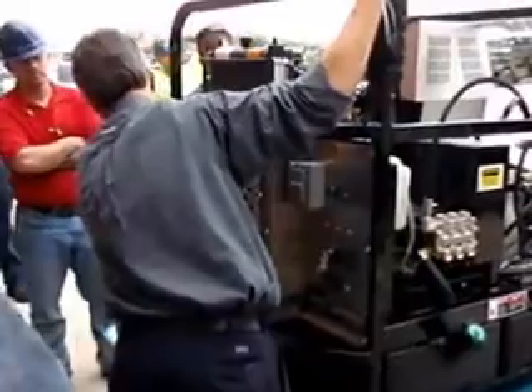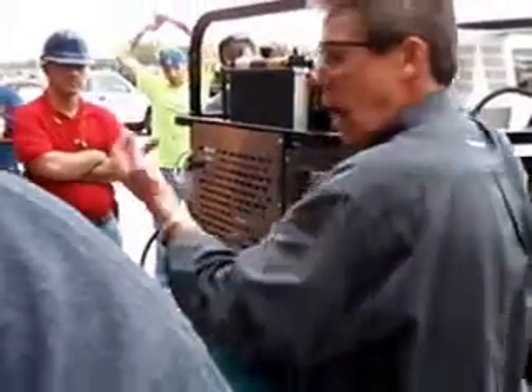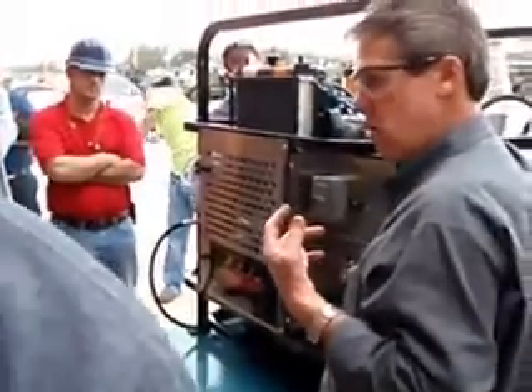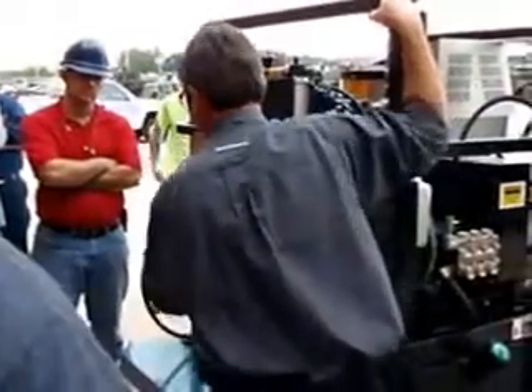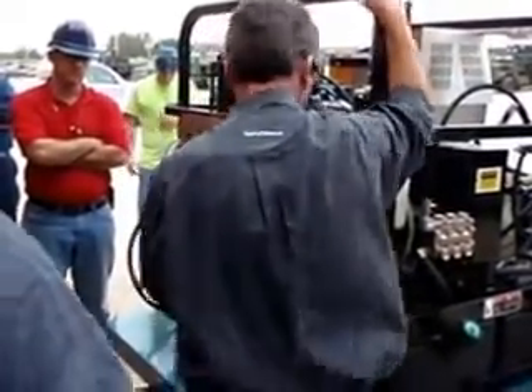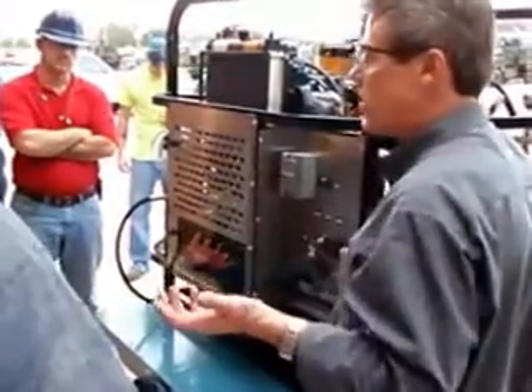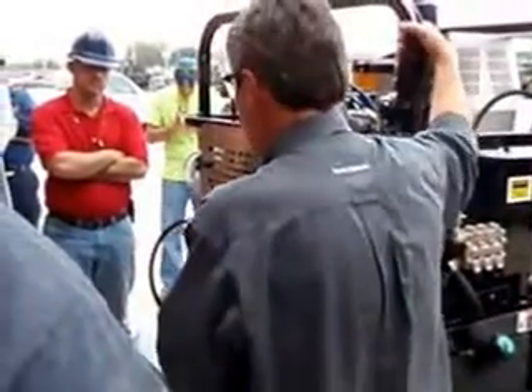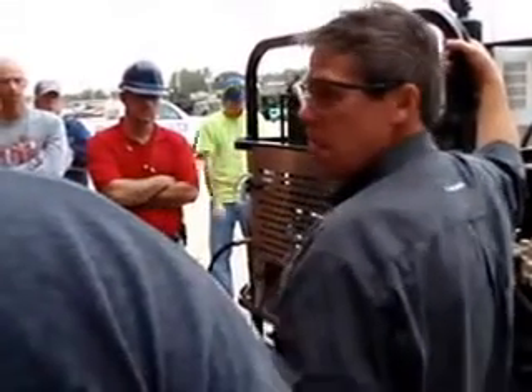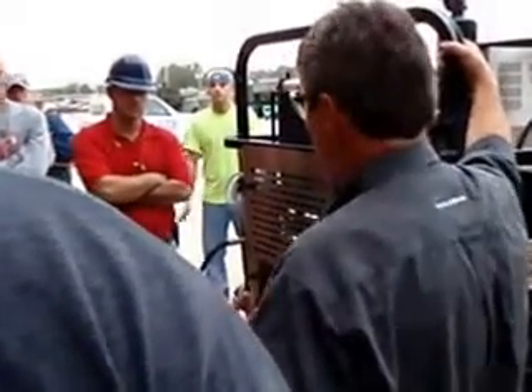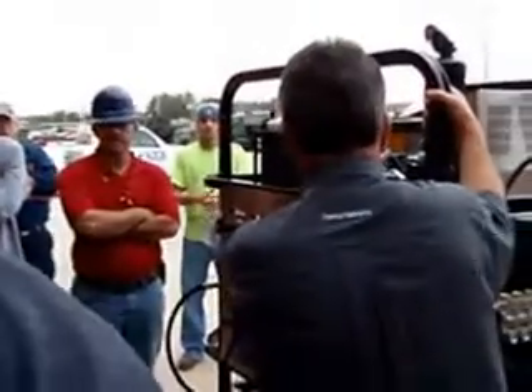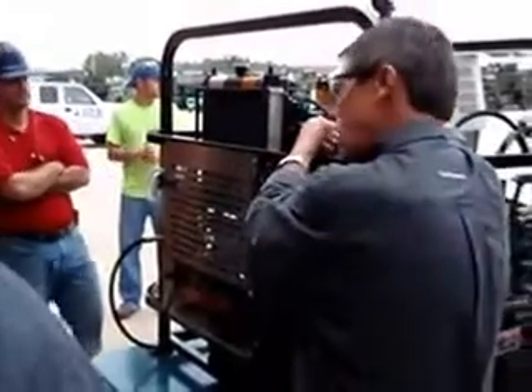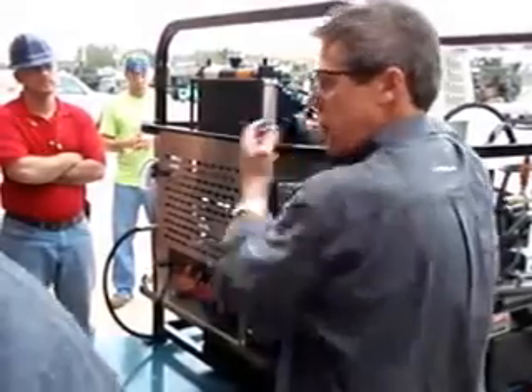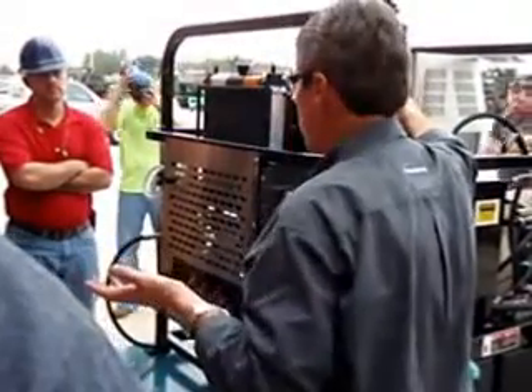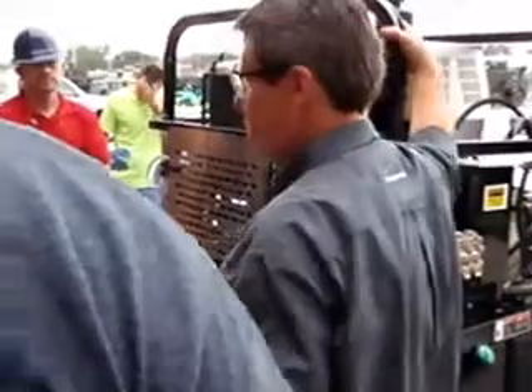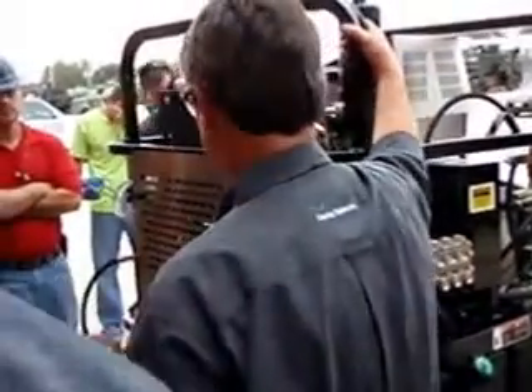So when I turn this valve, I'm bypassing some of the water. I'm not pushing all the water out through the system. I'm bypassing a little bit back to the pump head. So instead of 6 gallons per minute, you're running more like 5. Opti does 4, or 4.4 actually. By that, the burner's still trying to heat 6 gallons of water per minute. You cut it down to 5, so ergo you get a wet steam. It's kind of a steam, not a true steam vapor. It's called wet steam.